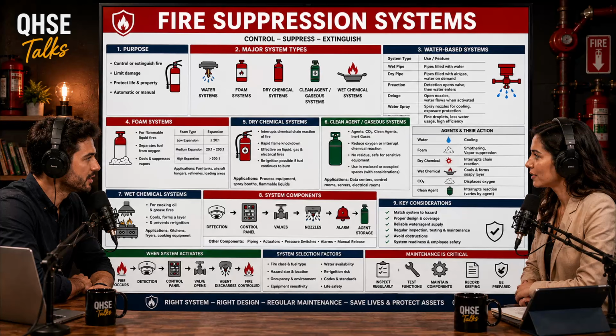You can't just hope nobody is in the room. You rely on strict engineering controls. Any CO2 system installed in an occupied space absolutely requires pre-discharge alarms. These are blaring sirens and strobe lights that trigger the moment smoke is detected. The system has a built-in time delay, usually 30 to 60 seconds, giving workers time to evacuate before the gas dumps. And what if maintenance workers are in there servicing the equipment?